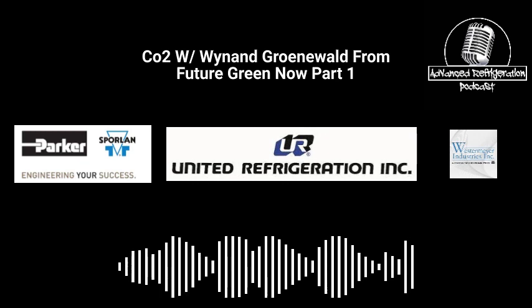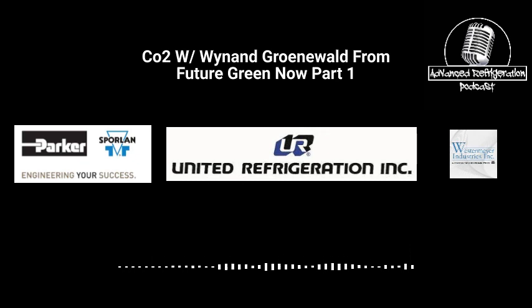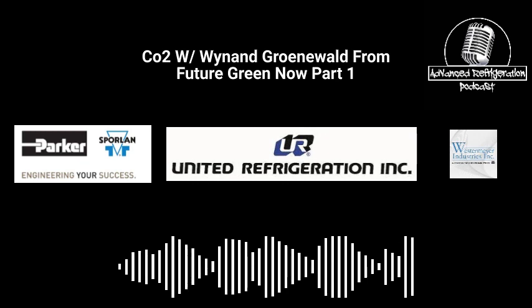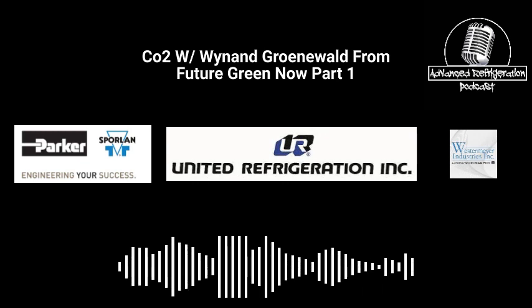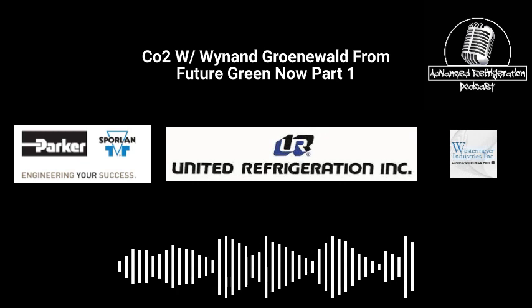So the second part of this, okay, this low ambient strategy that we've been messing with. Everything up here in the U.S., every manufacturer has been controlling the fans off of drop leg temperature. Now, we started to talk about this at AHR: why not use saturated condensing temperature? Use drop leg pressure and just convert it to saturation to drive the fans. And when you get to 87 degrees, where you're not going to condense anymore and you're running transcritical, just run the fans full bore.